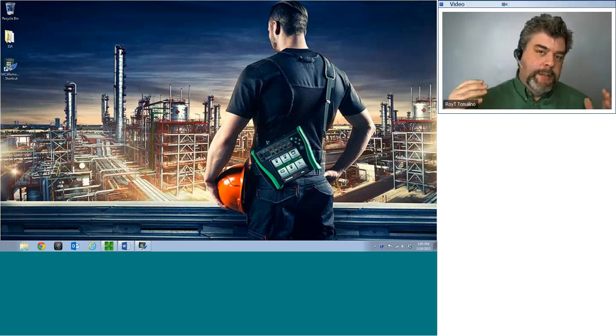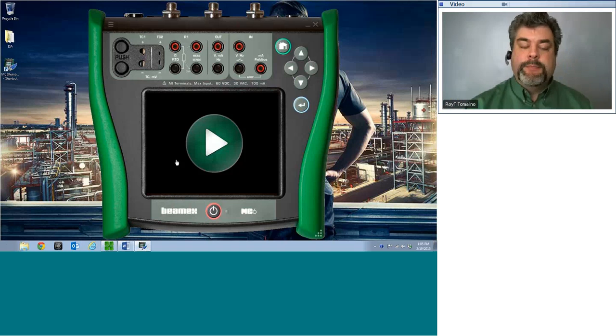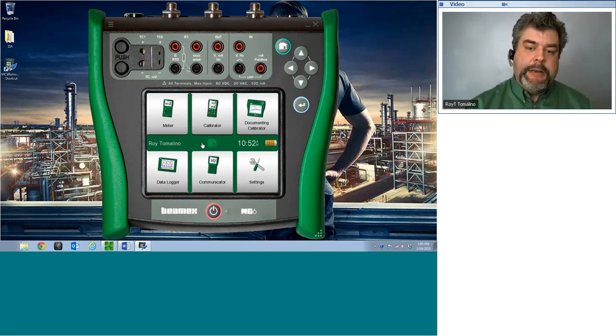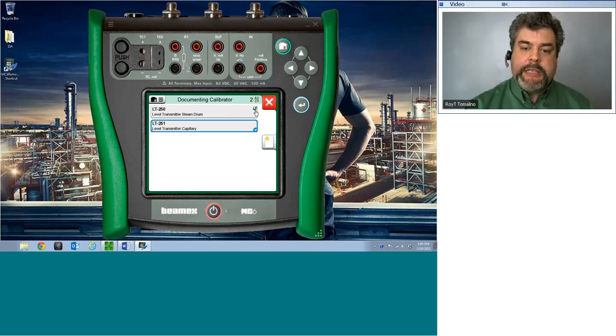So you are a technician. It's now time for you to do your second calibration. We go to the site, turn on your calibrator. Now, in this case, let me go into Documenting Calibrator. We've already done our first one. We can see a green check mark next to it. That means that we've tested it and it passed. The next one we have is LT-261, and this is our level transmitter with a capillary.